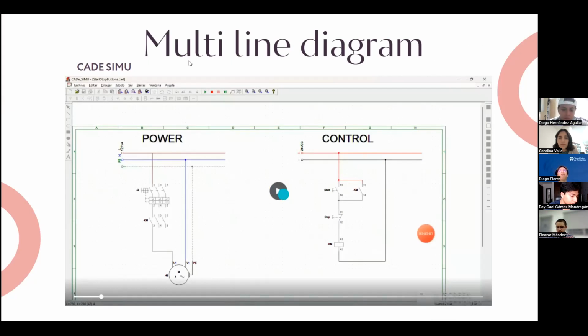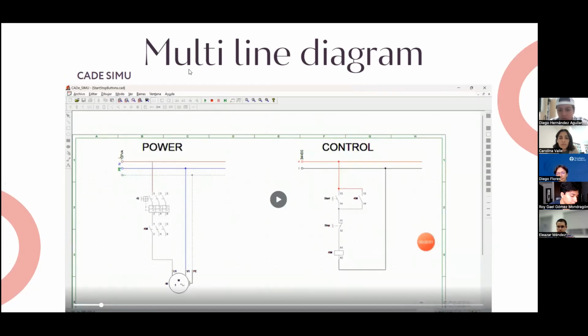We have two diagrams, one for the power circuit and another for the control circuit. In the power circuit, we have three principal wires: the power line, neutral, and ground. The brown one is the line with 127 volts AC, and it is connected to the circuit breaker and the contactor. Then we have the blue wire that is neutral and is connected directly to the motor in order to close the circuit. And finally, we have the green wire used to connect the motor to ground.